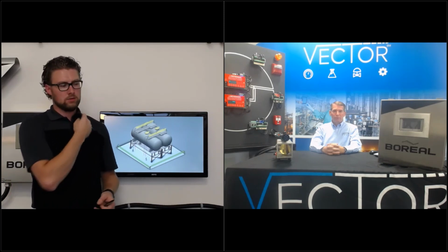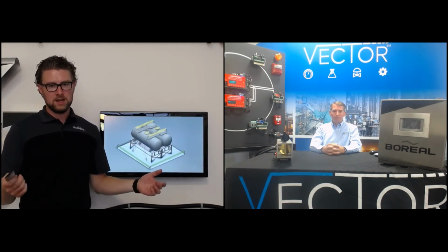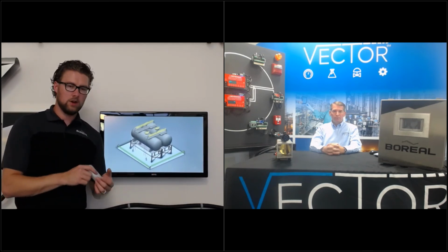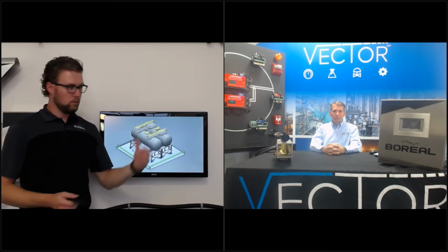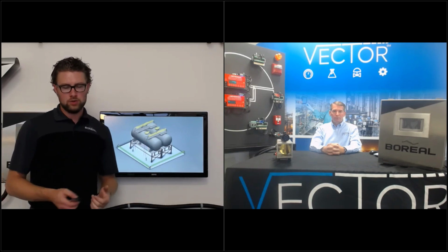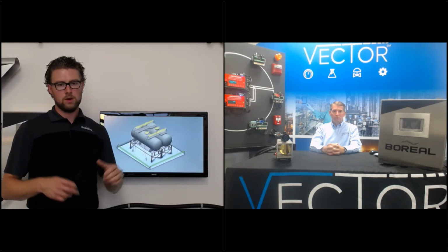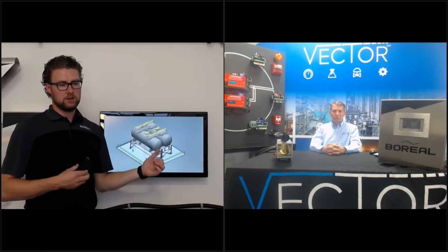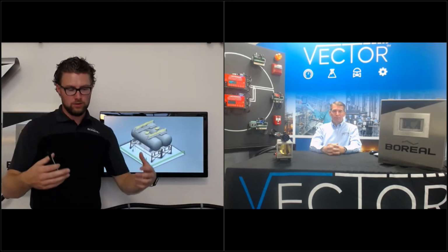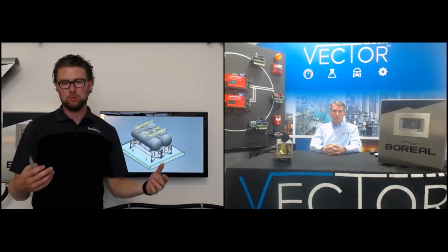So any sort of anhydrous ammonia handling, pumps, compressors, flanges, anything like that, is an ideal application for TDL. Traditional technologies have a hard time with ammonia, where TDL is ideally suited for those applications as well. So the great part about this particular technology, even for ammonia applications, is ammonia is devilishly difficult to keep in the pipe.